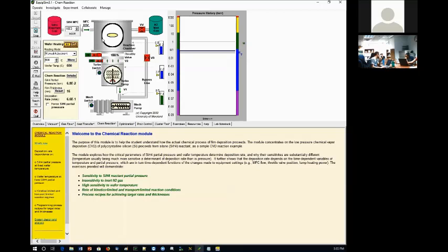So this is really now very high, but not extremely high either. Because see, it's only 68 millitorrs. So that's still not very high. If I add one more, that's going to make it 0.72 torrs. So these are large numbers.